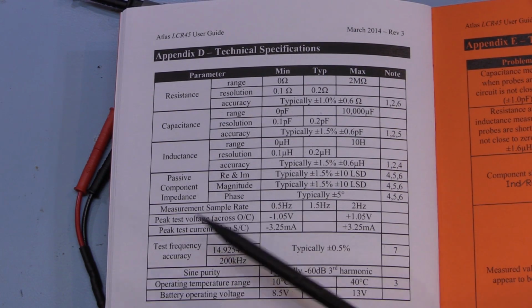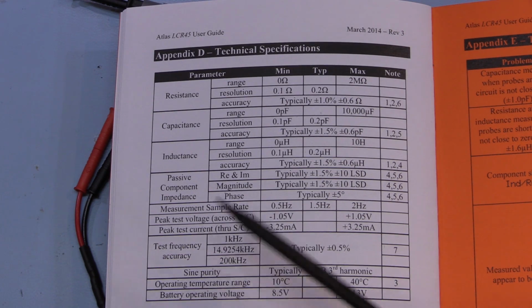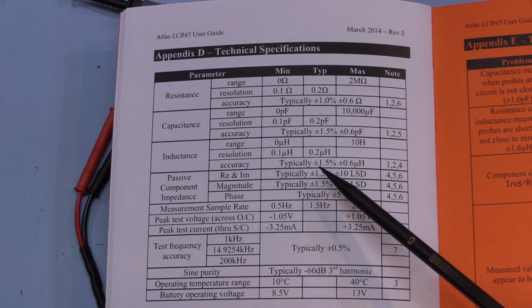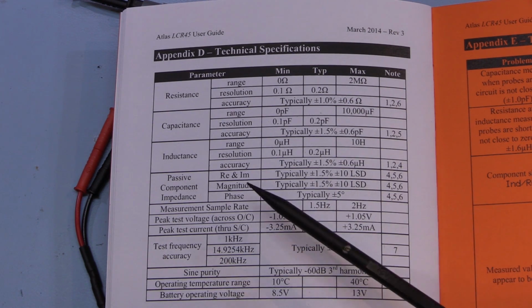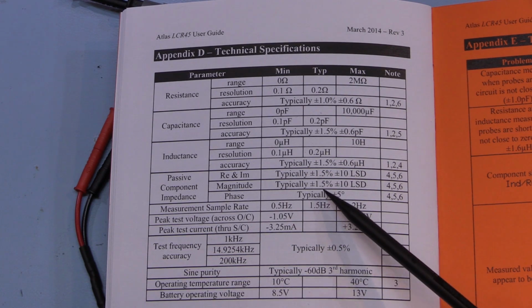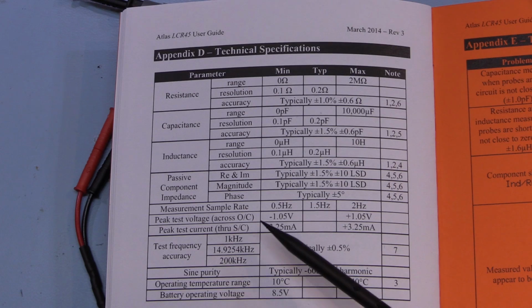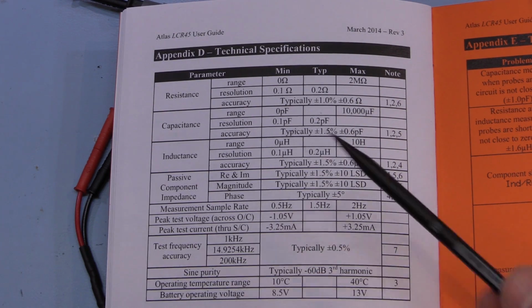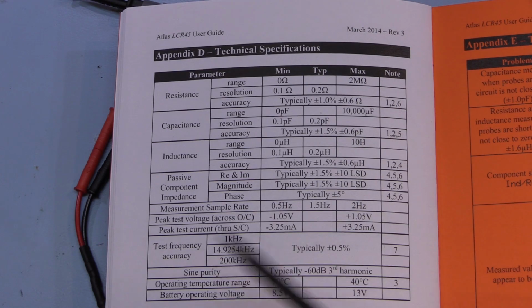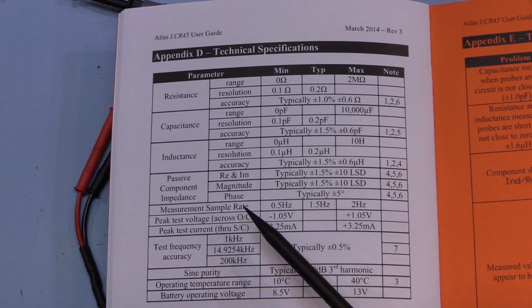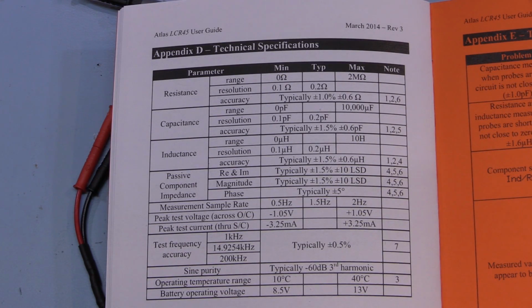And then we have the passive component impedance. For the real and imaginary parts, when you're reading the impedance, it has an accuracy of 1.5% plus or minus 10 least significant digits. The magnitude when reading the impedance is 1.5% plus or minus 10 least significant digits. And for the phase measurement, we've got a plus or minus 5-degree accuracy. It reads the actual values of impedance and LCR at a rate of 1.5 Hz, although there is a bit of tolerance on that. The maximum voltage that you're going to see on the test probes is plus or minus 1.05 volts, and a maximum current of plus or minus 3.25 milliamps. So some of this will make a bit more sense when we have a look through the manual at how this device actually measures complex impedance.